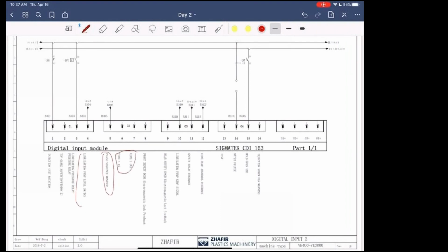You have core 3 in and out. Front safety door, if you have an electric door. Rear safety door with the electric door. What those do is keep the doors from opening after you put the machine in cycle. It locks the door with an electronic lock. Loop pump, safety relay feedback, core pump abnormal, water filter, which isn't on these machines, mold open end, injection screw fan warning.